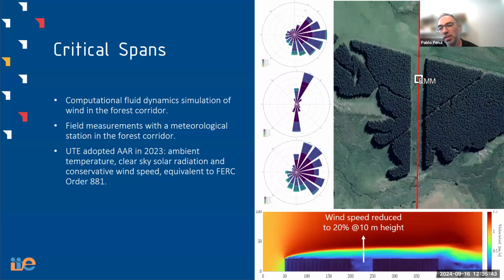So we conducted computational fluid dynamics simulation and installed a meteorological station within the forest corridor to understand this phenomenon. This effort confirmed that wind speed within this forest corridor is nearly zero and aligns parallel to the transmission line, which means there is minimal cooling. Based on this finding, last year, the Uruguayan transmission system operator, UTE, adopted the ambient adjusted ratings as a first step in the adoption of dynamic line rating. This approach, while conservative in wind speed estimation, allows for increased capacity utilization, especially during winter and nighttime when cooling demands are lower.